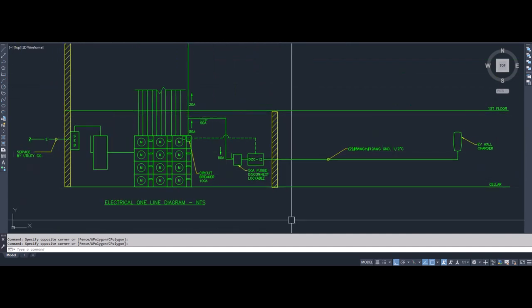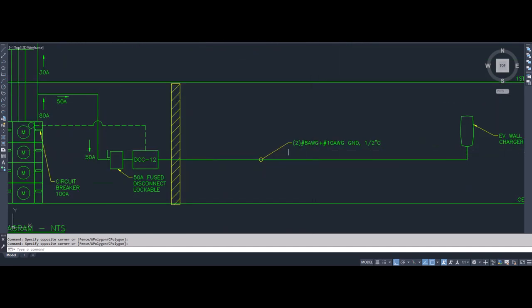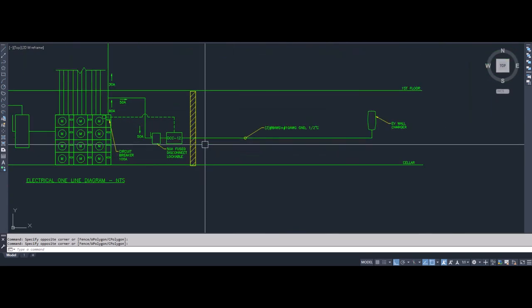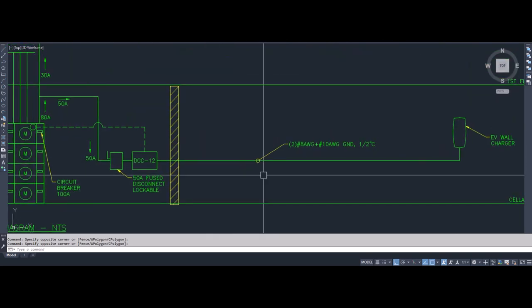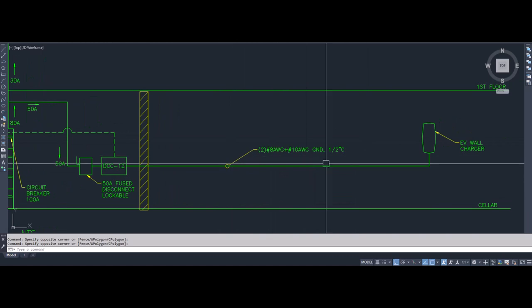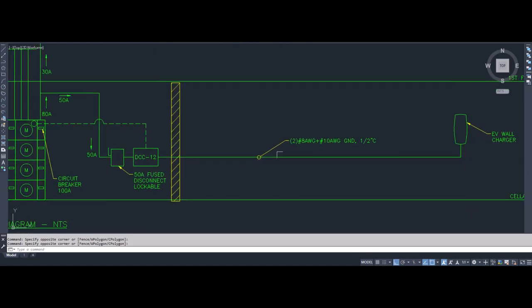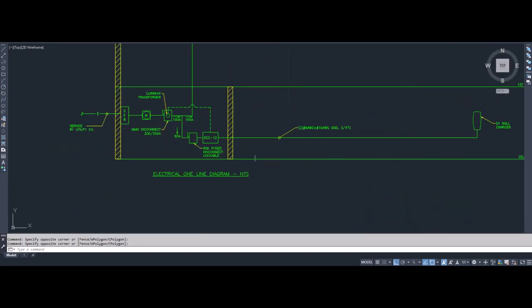So in these situations, the wiring is going to be sized based on the NEC, and I show it here. But basically, I'm just going to run through one example, not so that you install the wiring yourself, but to check the wiring that was done by the licensed electrician. All right, you need to make sure that you hire a licensed electrician to do this work. And I'm just showing you this just to see if their work was done properly. So to size the wiring and the conduit size, you have to use the NEC table. So for example, let's look at this one.